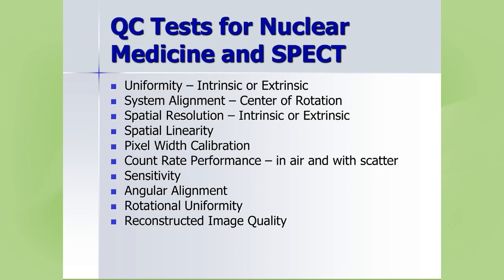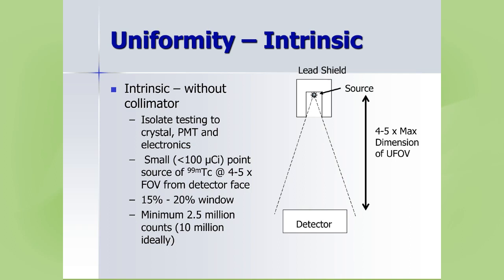Moving to NucMed/SPECT: standard tests include uniformity, system alignment or center of rotation, intrinsic or extrinsic spatial resolution and linearity, plus others performed more ad hoc. For intrinsic uniformity, we pull the collimators off to isolate the crystal, PMT, and electronics. We make up a small less-than-100-microcurie point source of tech, positioned four to five field-of-views away from the detector face, and acquire a minimum of 2.5 million counts — ideally closer to 10 million — with a 15–20% energy window.